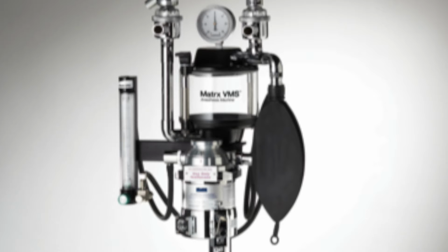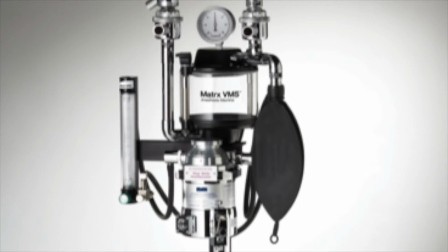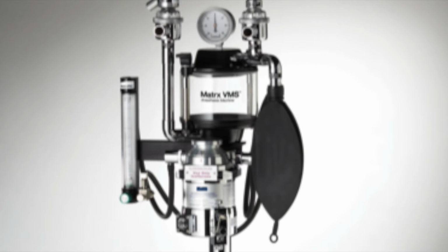Then it is connected to the oxygen flush valve, which allows oxygen to bypass the flow meter and vaporizer and enters into the system at 40 to 70 liters per minute. It is designed to allow the anesthesia circuit to be filled with anesthetic-free oxygen very quickly.